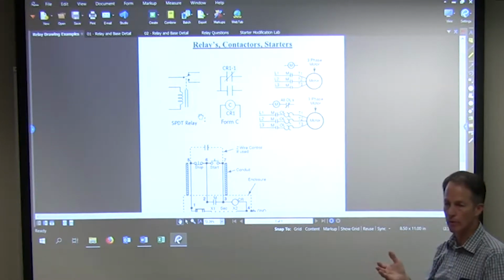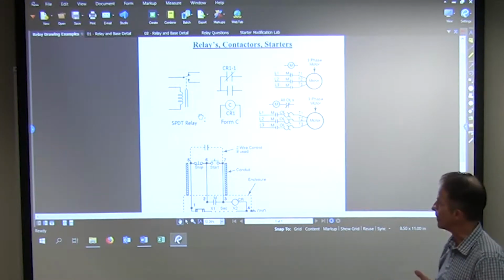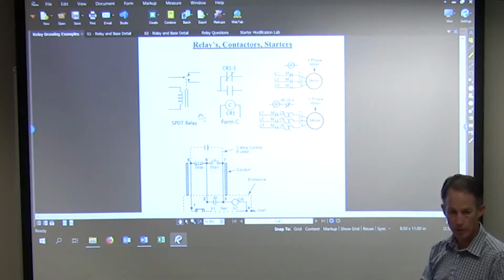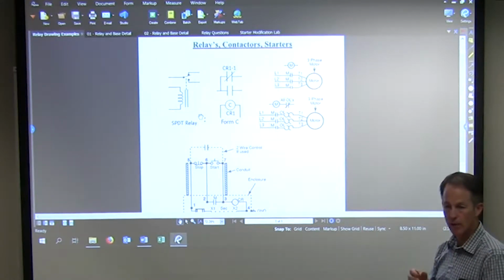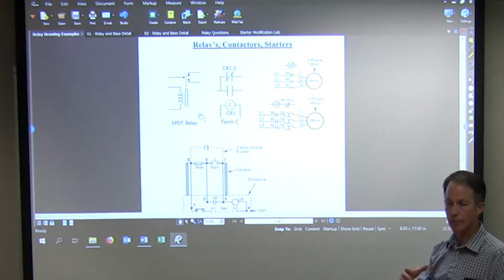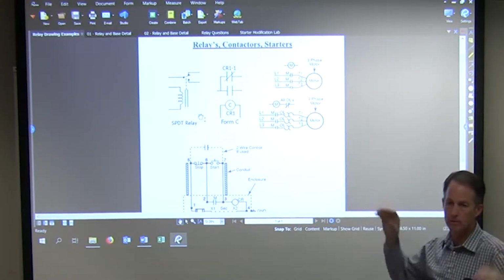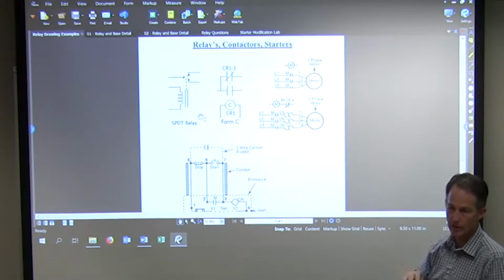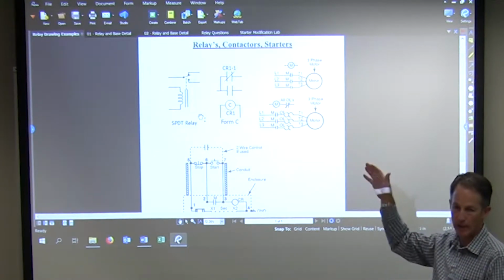They could be 24 volts, we use that quite a bit. Sometimes 120 volts. We try to do all of our 120 volt switching on newer panels outside of the panel, and do 24 volts inside. We try to keep the higher voltage out of the panel.